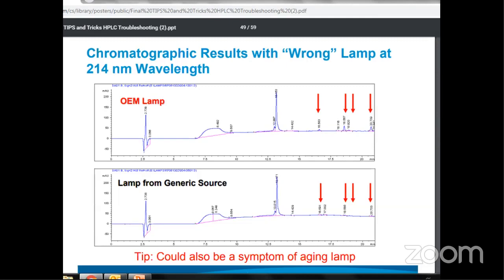only that lamp. If you use a generic source, meaning in the market you'll find a number of companies or small vendors providing lamps, ask for a certificate of authenticity. It's not meeting compliance either. If you are using such a generic source and it's not providing a certificate or a test, it's simply giving you a lamp and saying please carry on with this lamp. It will work for 2 or 3 months. Please, I request you not to use those lamps.